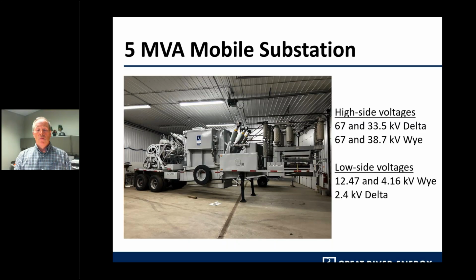Shown here is our 5 MVA mobile substation located at our Dickinson's plant, or substation, in Buffalo, Minnesota. As you can see, there are different high side voltages and configurations, and also low side voltages. Going from the right to the left of the picture, that's where our high side connections and bushings on the transformer are. Then it goes through the transformer to the low side, or X bushings, down through the recloser and to the metering CTs and PTs, and then to the cable reel on the back of the mobile. Looking at the low side voltages, there's a 2.4 kV delta low side configuration, which was designed at the time.